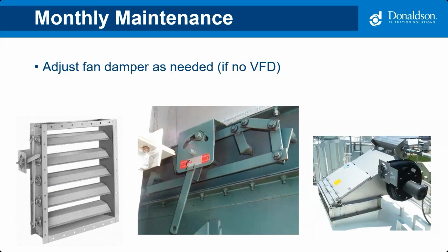And the last thing, I mentioned earlier about a variable frequency driver, a fan speed controller. And so if you have a VFD that's controlling fan speed, basically as your filters load from being brand new and that 0 to 2 inches of water to seasoned at 2 to 4 inches of water, that VFD is going to automatically moderate the fan speed to maintain the flow per the design.